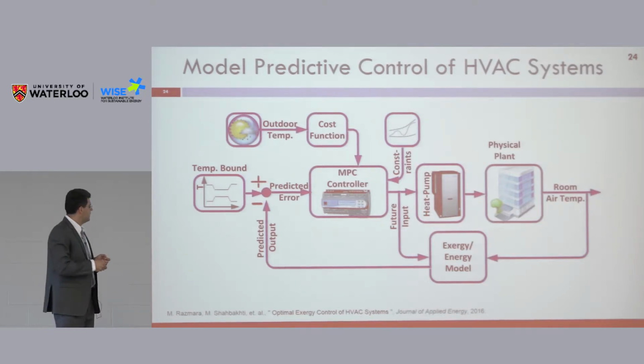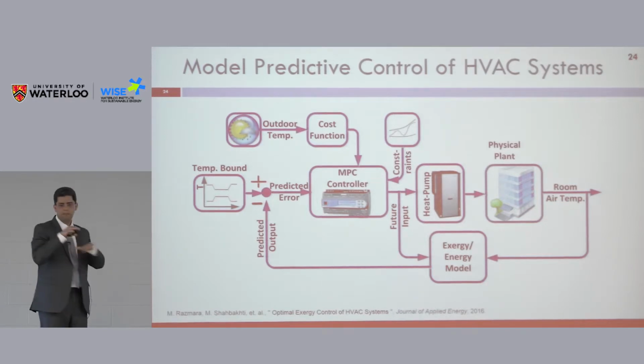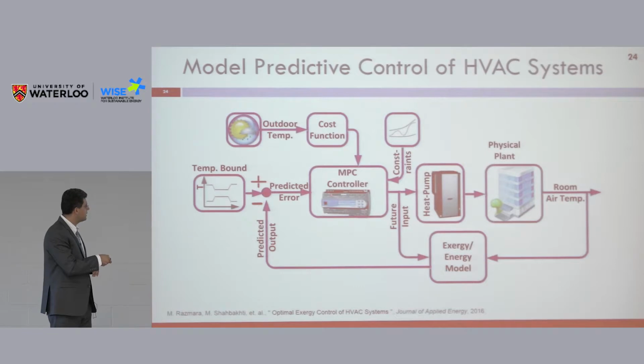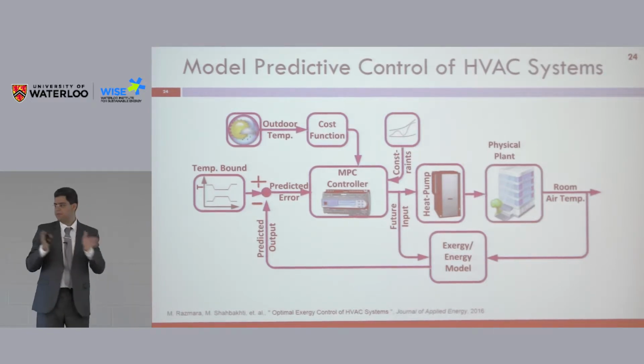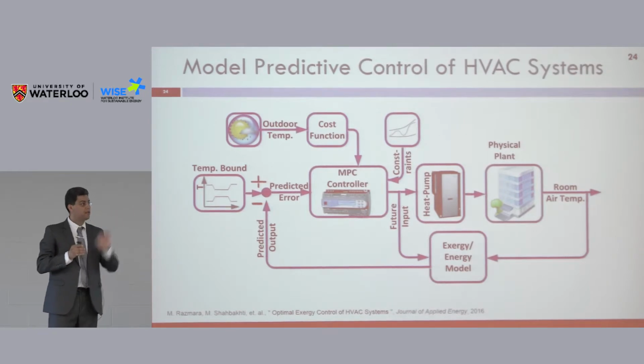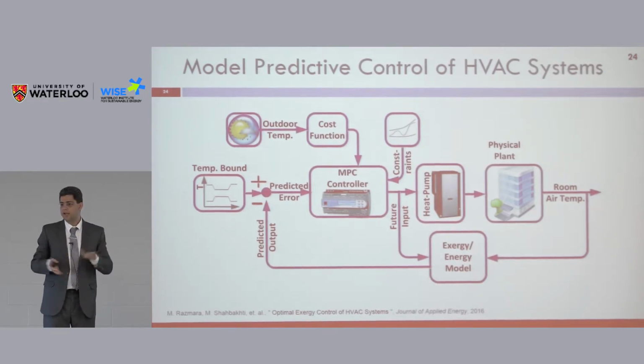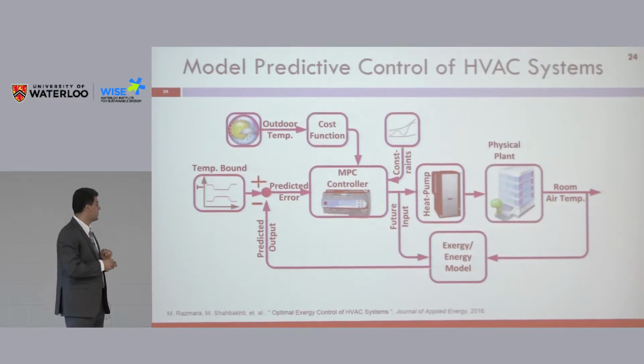Then you will see what is the desired temperature. You usually have a bound coming from the ASHRAE standard, and then you control it with the MPC controller. You also know what are the constraints you have. For example, if I have an actuator, I cannot get the flow rate here to become super high. If the temperature was cold, I cannot get -5 degrees coming out of that. So there's a lot of actuator constraints there.